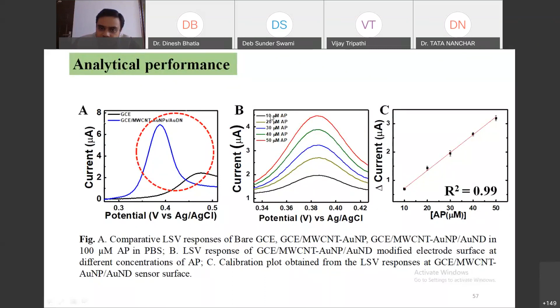We have increased the concentration of acetaminophen from 10 to 50, and there is a straight line forming, which shows a very good correlation between the data. So this is the final calibration where the concentration has been increased from 100 to 7,500, and there is a very clear-cut increase in the signal. You can see from this calibration plot, and the response time is about 10 seconds. I mean, we have done multiple testing. We can say about 8 to 11, 12 seconds. The response time is there. So this response time is basically attributed to the presence of these nanostructures in the matrix. Otherwise, if you remove the nanostructure matrix, there will not be such robustness in the system, right?